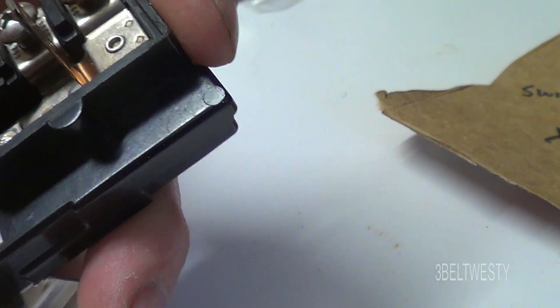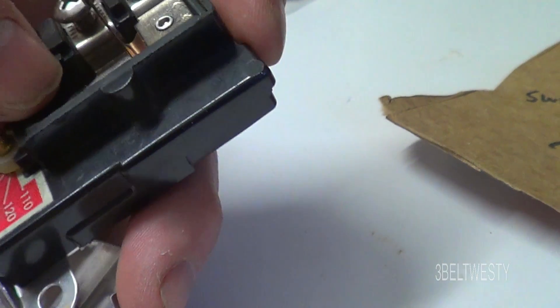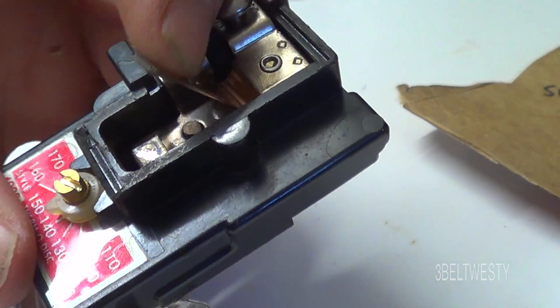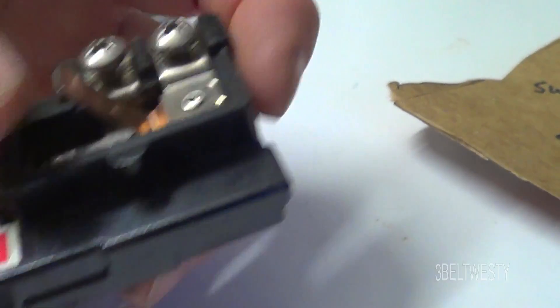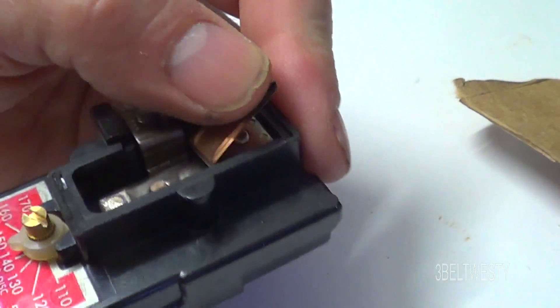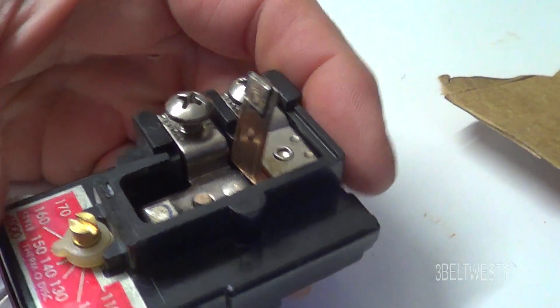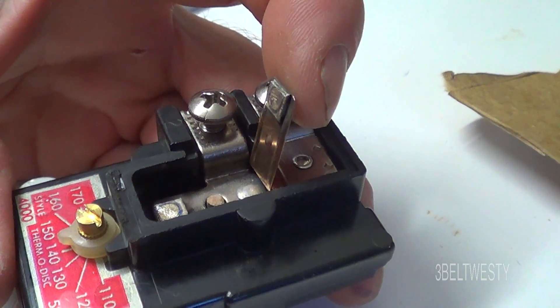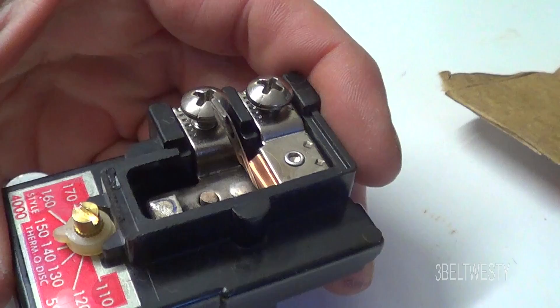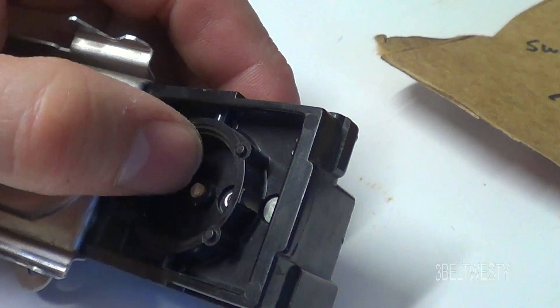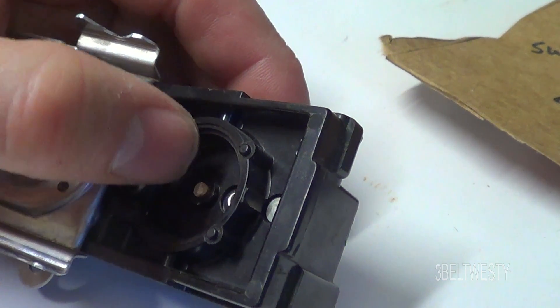And the disc on here probably got stuck once is what happened. And then it started to arc because it wasn't completely off or on. And then that heat got through and then screwed up the plastic even more, and then it just seized up on there. It's just kind of like thermal runaway. And so it shows that it may have been when they molded that plastic piece, they had too much water in the pellets and so they got a bad batch.